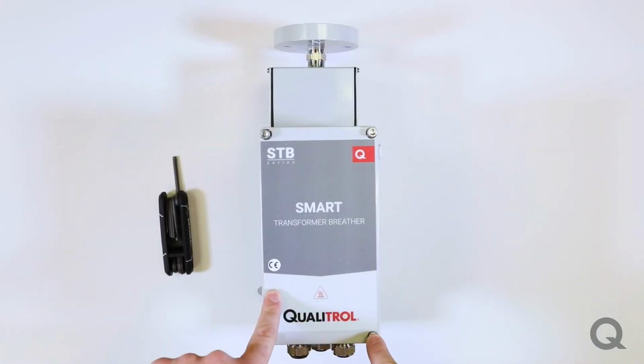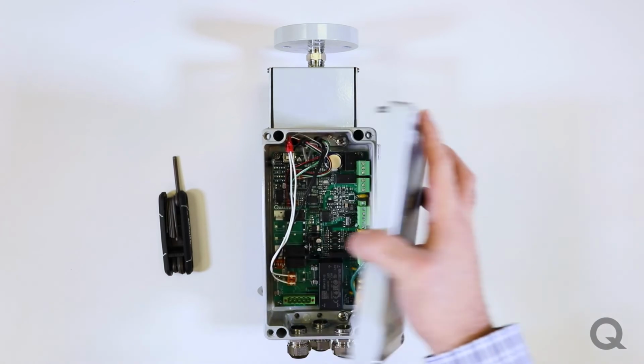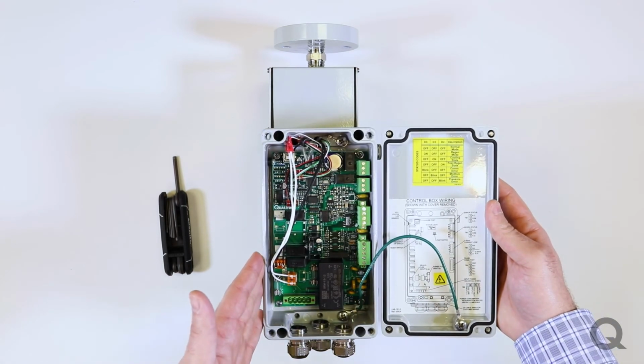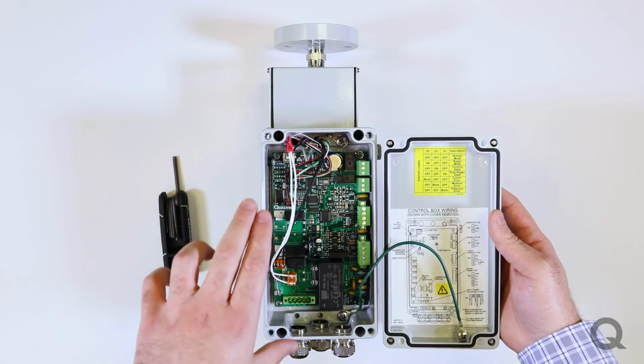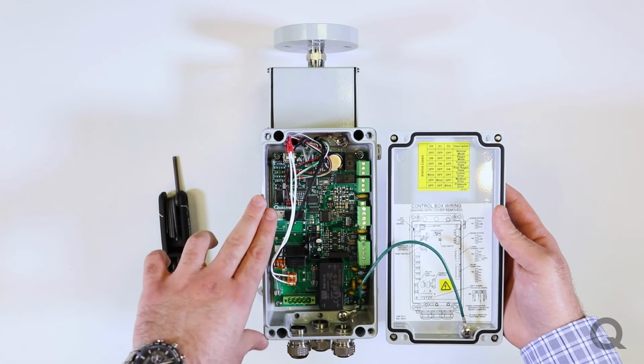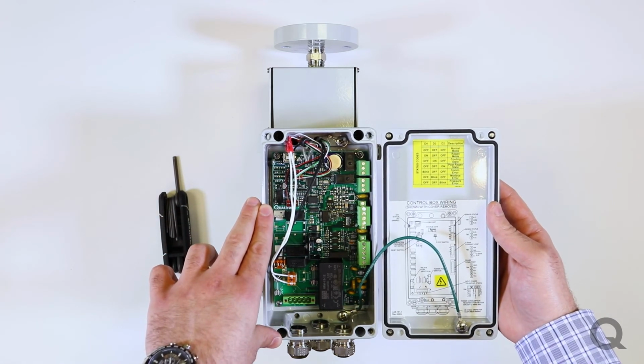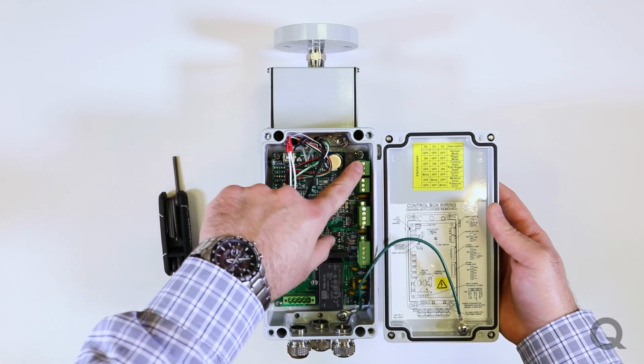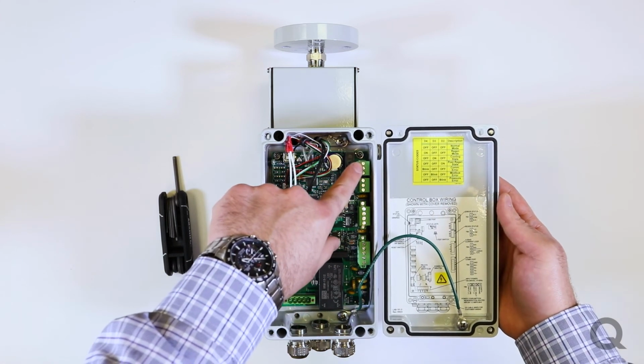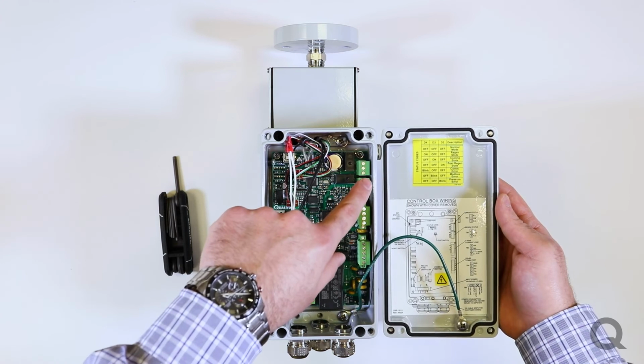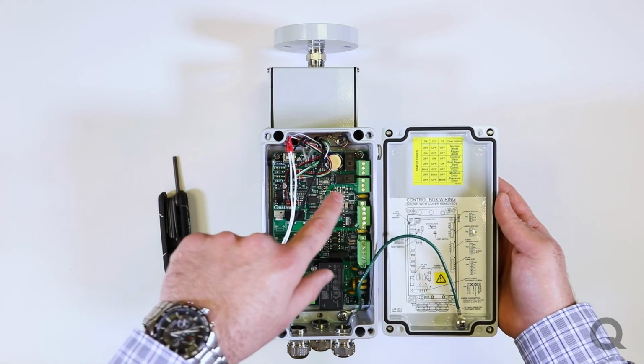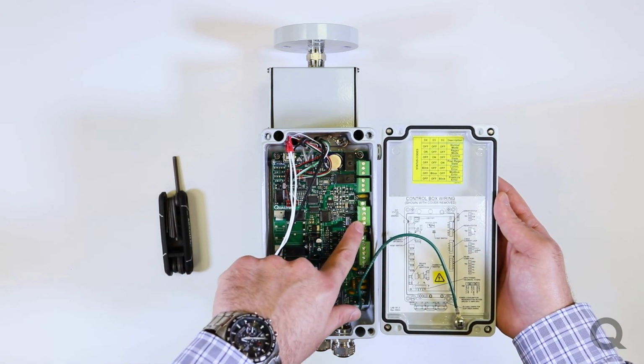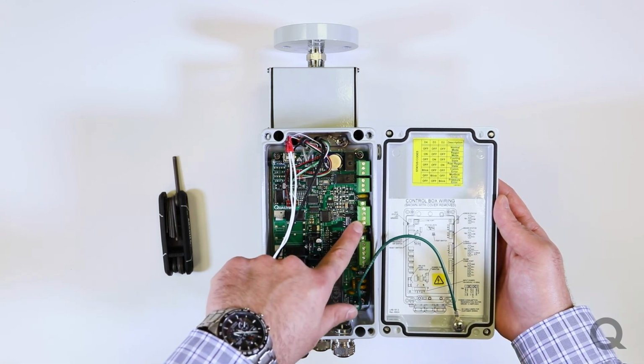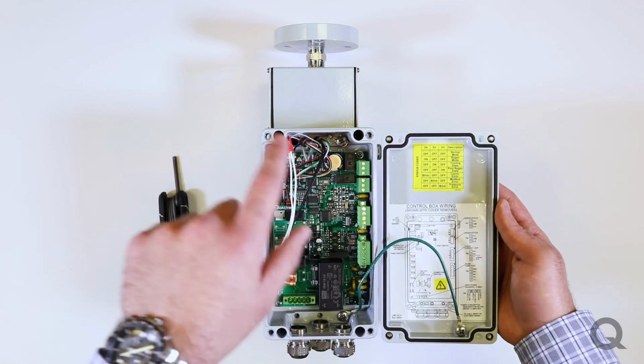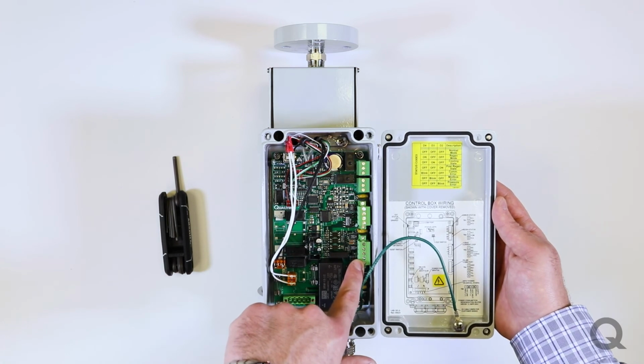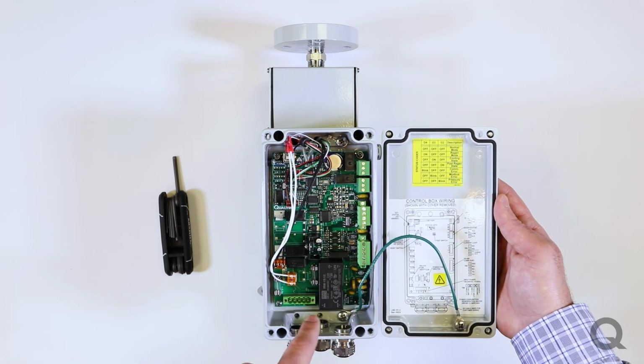So taking a closer look inside the new breather, you can open the enclosure with 4 5mm hex screws on the enclosure cover. So we'll take a closer look at some of the wiring inside of here. As we spoke earlier, this is a model with the added communications and data logging feature. So we'll start up here on the right, on top side, you have your error status relay. Moving down, you have your regeneration status relay. This is the current loop output, so the 4 to 20 milliamp output for the relative humidity percentage of the desiccant. Moving down even further is the RS-485 communication port, and that's where the Modbus can be connected to.